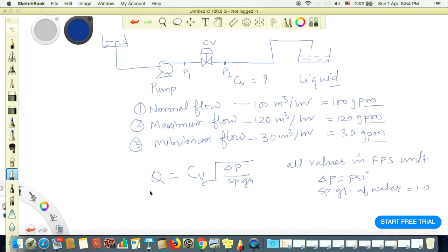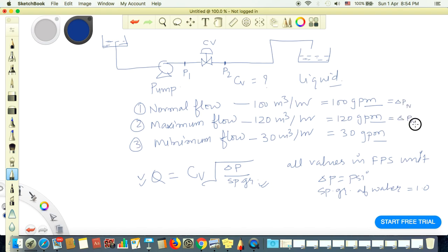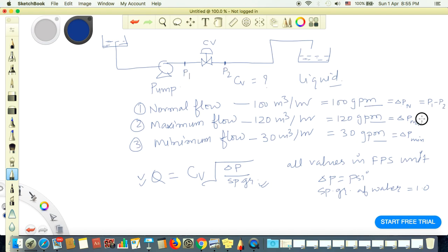We know the formula and the flow values, but we don't know delta P. Delta P is what we want to find: delta P normal, delta P maximum, and delta P minimum. These are the differences between P1 minus P2 — the upstream and downstream pressures — for each flow condition. Once we know these values, we can calculate the CV value of the control valve.